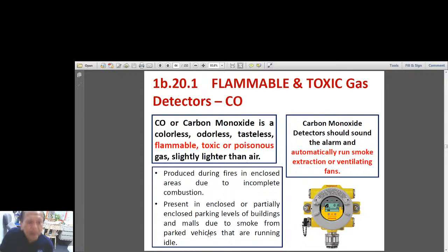And that makes it poisonous or toxic. Carbon monoxide is produced during fires in enclosed areas. So, if you have a fire inside air-conditioned or enclosed rooms, chances are you produce this carbon monoxide. It is present in enclosed or partially enclosed buildings when there is not enough oxygen inside, and when there is a parked vehicle running, chances are you also produce carbon monoxide. So what is the solution? You must have detectors. This is the only way. We must have a carbon monoxide detector that actuates an alarm and runs an automatic extraction fan, exhaust fan or ventilating fan, so that the carbon monoxide will be flushed out from the room.